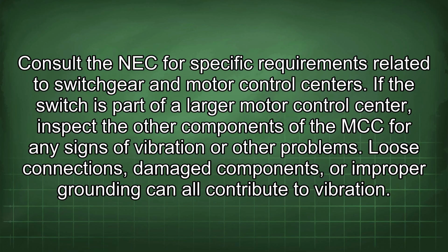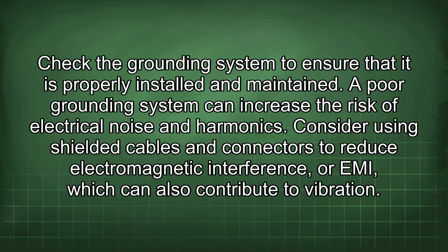If the switch is part of a larger motor control center, inspect the other components of the MCC for any signs of vibration or other problems. Loose connections, damaged components, or improper grounding can all contribute to vibration. Check the grounding system to ensure that it is properly installed and maintained. A poor grounding system can increase the risk of electrical noise and harmonics.